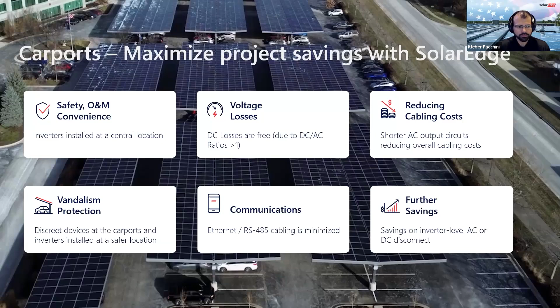Savings in communication cable. Instead of having to wire RS-485 Ethernet cable to all of the inverters, everything is together, so you don't have to bring communication cables into your array. This reduces cabling costs since you're running DC cables instead of AC - two cables instead of three. Voltage losses are more forgiving on the DC side, so you can have a higher DC loss than on the AC side because of the high DC to AC ratios.